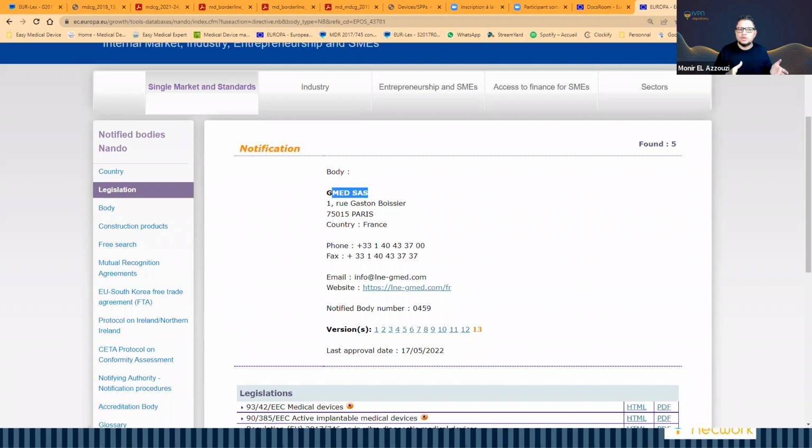So this is the point where now it's a medical device, because there is software that will manage all the images, maybe contrast, maybe analysis of it. But a screen alone, even if it's used in hospitals, is not a medical device. And this is mainly the thing that people are misunderstanding. Yeah, there is no risk in having a screen. It's a screen. You can watch TV on it. You can play games on it. It's just a screen. You make it a medical device when you include a medical device in it. Then it's a medical device. But before that, it's just a screen.